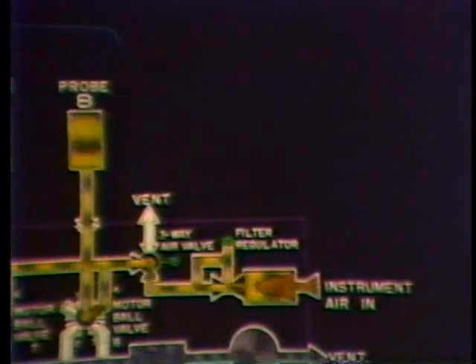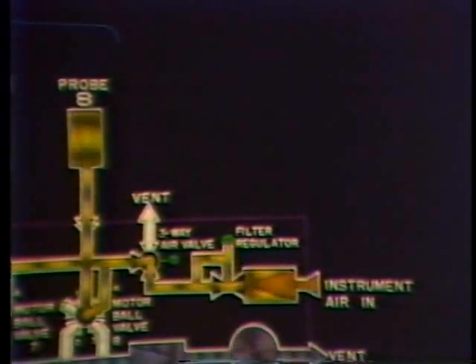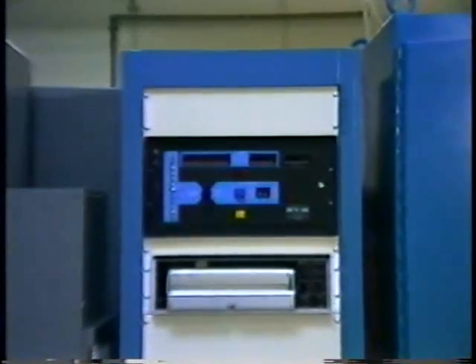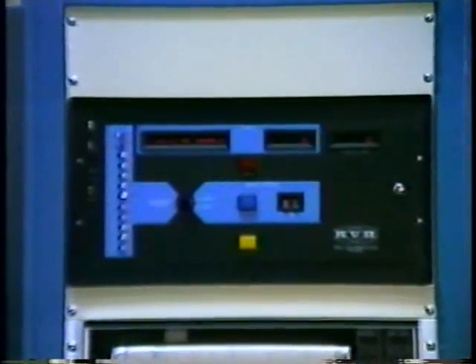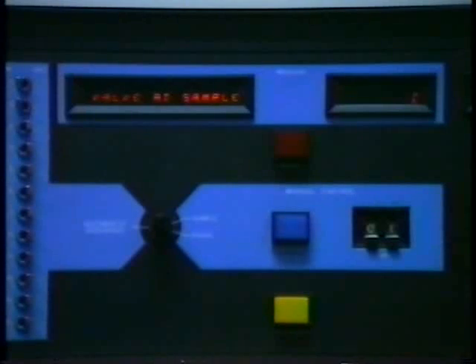To keep the filters and lines clean from coal dust, each probe is automatically purged upon completion of its sampling assignment. Instrument air forces coal particles out of the probe, cleaning it for future sampling. A vacuum switch is activated if clogging should occur. At the control panel, the microprocessor communicates with the operator by contact closures and bright alphanumeric displays. Other configurations are possible. During normal operation, the probe currently being sampled will be indicated in the message display. Real-time results of analysis for this hazardous location are displayed numerically in parts per million.